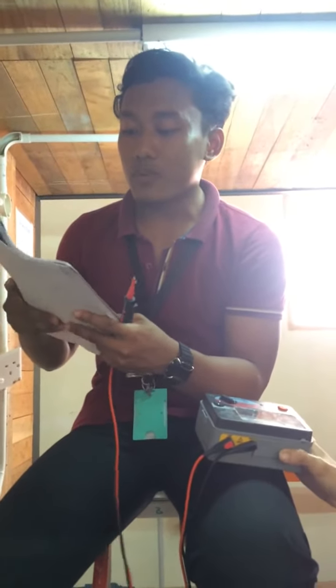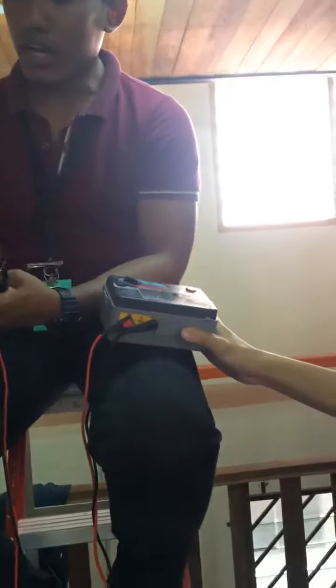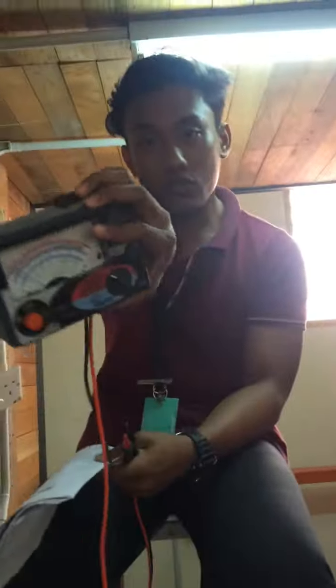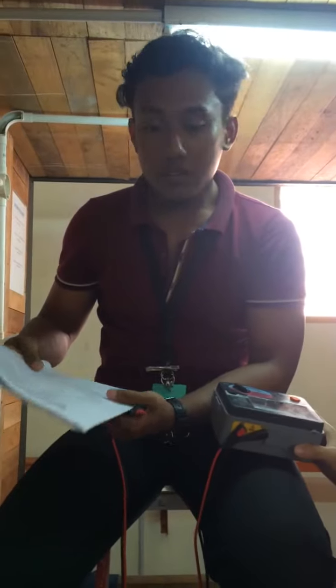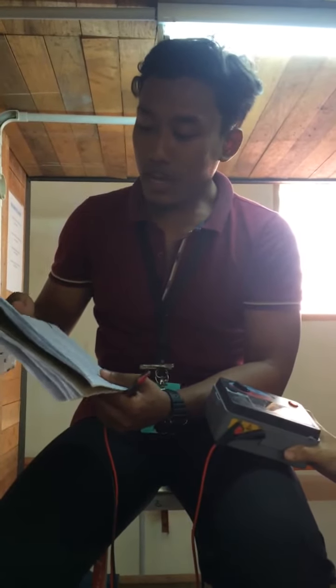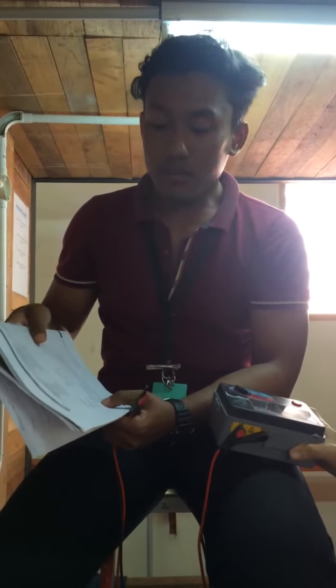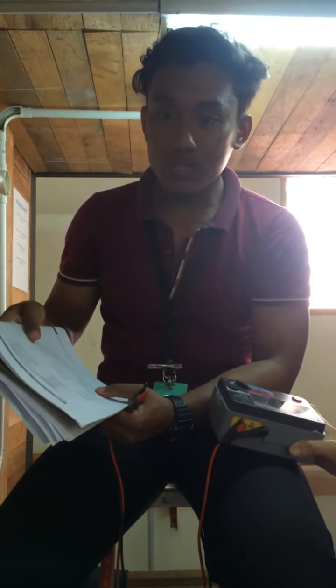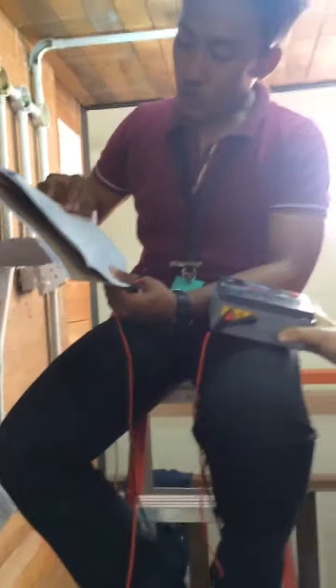The equipment that we must have is an insulation tester 1 unit and a wiring trainer 1 unit. So this is an insulation tester, you can see here. And then the procedure: refer to the testing diagram figure 3.3 in this book. Ensure the main power supply has been switched off, including the main switch. Remove all the loads, switch on all the control switches, the switch for the light circuit, the switch for the light, and the switch for the socket outlet here, RCCB, and also MCB. Then number 4, do the testing procedure as per the instructions given in table 3.3.